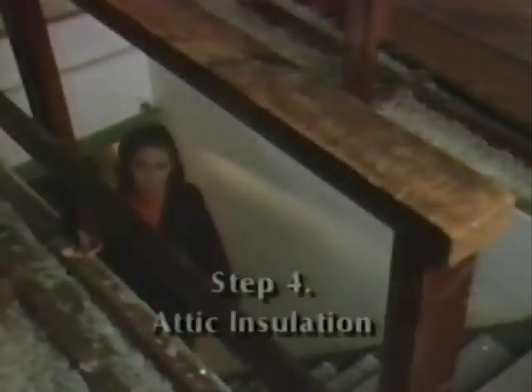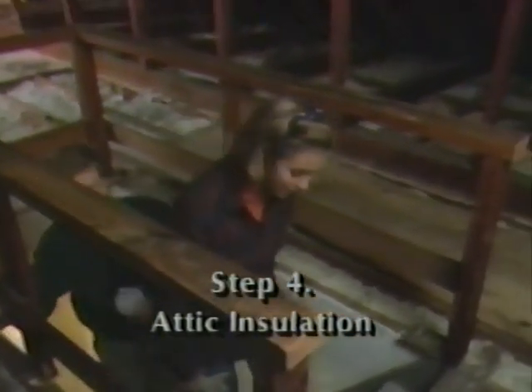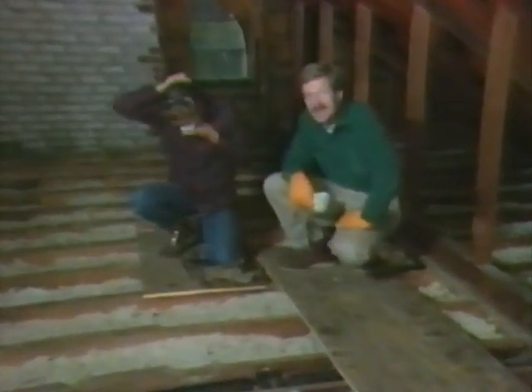When you start thinking about insulation, you should start thinking about your attic. Because hot air rises, one of the prime trouble spots for heat loss is the top of the house, and attics are usually under-insulated. When this house was first insulated, energy efficiency wasn't as important as it is now, so 5.5 inches of rock wool was considered enough. However, it isn't enough now, and the insulation has settled, which further reduces its R value, so it looks like more insulation is the order here. But before we insulate, there's two things we have to consider: sealing up bypasses and installing venting.